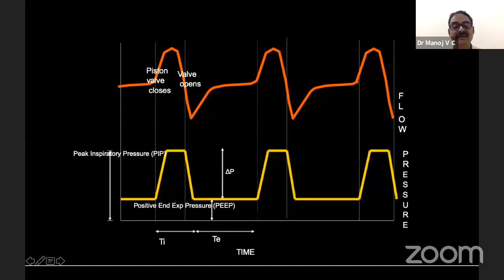So now you have learned three terminologies: PIP or peak inspiratory pressure, positive end expiratory pressure, and inspiratory time. Now after this, what happens? After the valve opens, it will remain open till the next breath starts, when the valve closes. So this is your expiratory time, and the total of inspiratory time and expiratory time is the full time for a cycle of breath. That is your time for respiration, or ventilator rate. I hope these concepts are clear. We can discuss further subsequently.